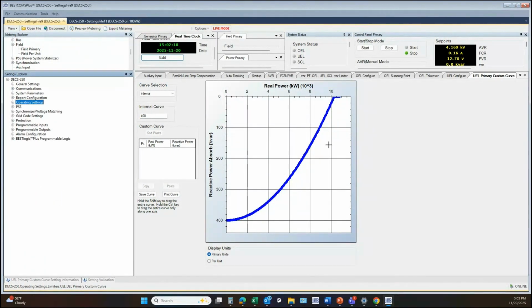And the rated data that I mentioned earlier, somebody had asked where you would find that. That comes from the OEM. Normally, there's a nameplate on the machine that has that data. But if not, then hopefully they provided some documentation that has that data. Otherwise, you will have to go back to the OEM to find that information for the rated voltage, rated current, rated power factor, rated kVA, your rated field voltage and current. It's not very common to have the no load, but normally you do find the full load field voltage and field current on the nameplate.